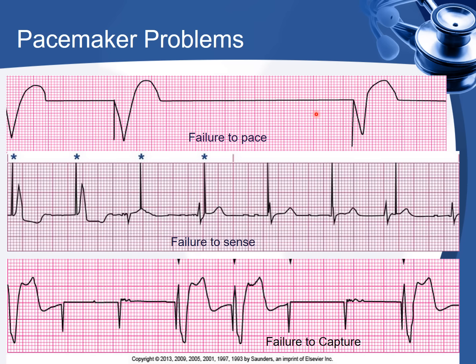Sometimes even if we change the battery, you still are going to see the failure to pace, and that means that something is wrong with that actual box or pulse generator, and so you do have to change that, and hopefully that would fix the problem, and we can go on. If you've done everything that you can and you're still having failure to pace, that would be the time to call your healthcare provider so that they can come in and do some more in-depth troubleshooting so that we can fix the problem.